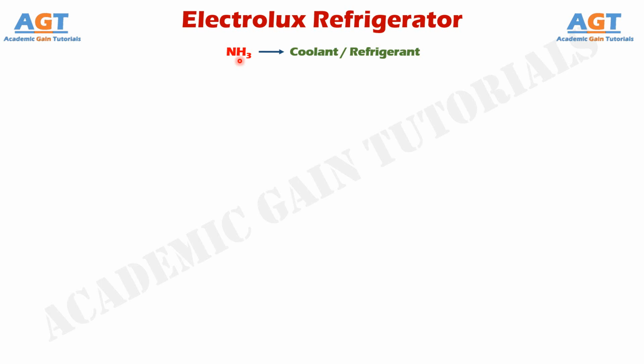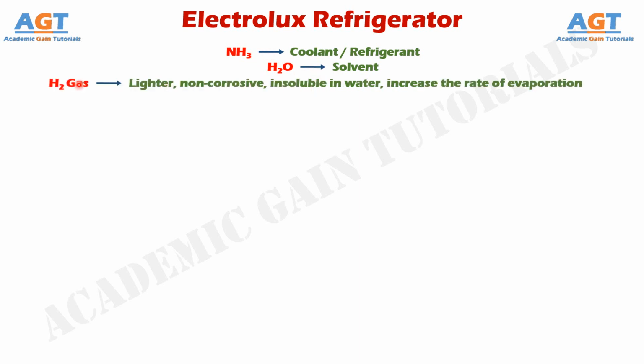And here our second fluid is water. We use water as a solvent here, because it has the ability to absorb ammonia. Since ammonia is soluble in water, our coolant ammonia flows through the Electrolux refrigerator system as a mixture with the solvent water, and changes state from liquid to vapor, or vapor to liquid, at convenient temperatures for the refrigeration cycle. We use hydrogen because it is a very light gas, and helps to increase the rate of evaporation. It is non-corrosive and insoluble in water. The lighter the gas, the more will be the rate of evaporation. So, these are the 3 fluids that we need to run the whole process.